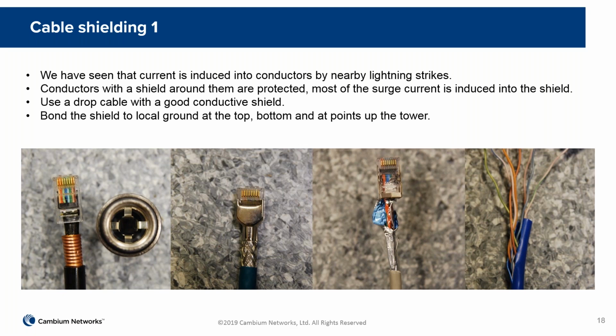I've got a picture there of a screened cable, and this is pretty well as good a way of protecting the inner cores of the cable. A little trickier to make off effectively. We've enclosed the screen underneath the connector, the back shell of the connector, so that's been crimped on, and we need to find a way, which we can do with the gland on the left there, to get that energy that's flowing in the outer again down to ground. So that's a reasonable solution.